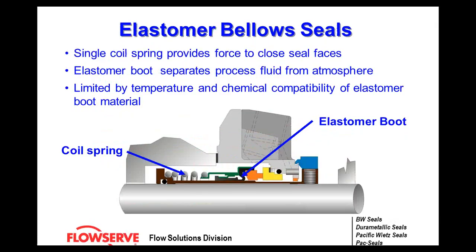Elastomer bellows are a variation of the pusher seal — you have coil springs which apply the closing force, and an elastomer boot that separates the process fluid from the atmosphere, limited to the temperatures and chemical compatibility of the elastomer. Elastomer bellows are a bit more forgiving to movement than a regular dynamic o-ring on a pusher seal, allowing for a little more axial or radial movement. You'll see these in general service seals.